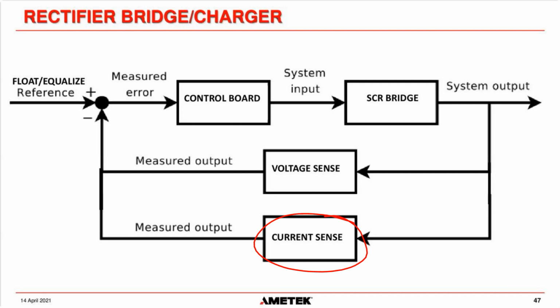We have a current sense circuit, and the current sense circuit actually overrides the voltage sense circuit. So let's say that the SCR bridge could do 100 amps. In other words, the SCRs that we installed in the bridge are designed for a maximum capacity of 100 amps. So if we go above 100 amps flowing through those SCRs, they could be damaged. So obviously we don't want to go above 100 amps. And remember, this is just for ease for you to see. We actually overrate our SCRs. For 100 amps, we would put 200 amp SCRs in our bridge. But this is just an example.